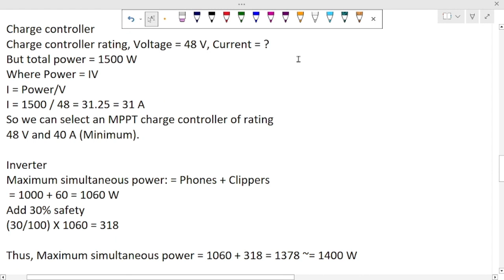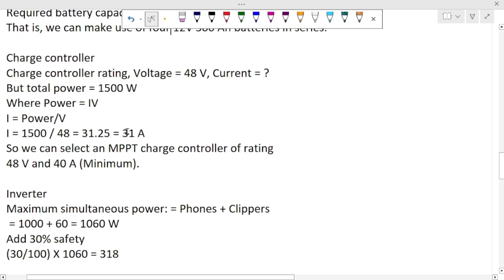Change your subject of formula. V goes down, power over V. So I equals what? Power over voltage. Power is this, voltage is this, and that will give you 31.25, approximately 31 amps. So we can select an MPPT charge controller of rating 48 volts and 40 amps. That's the minimum. It should be more than the calculated value.